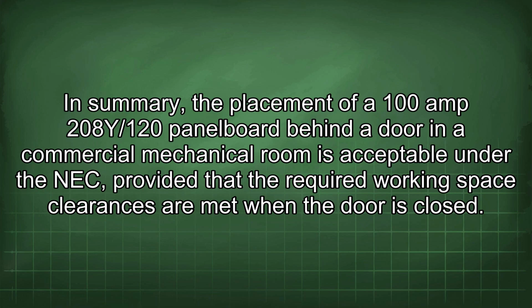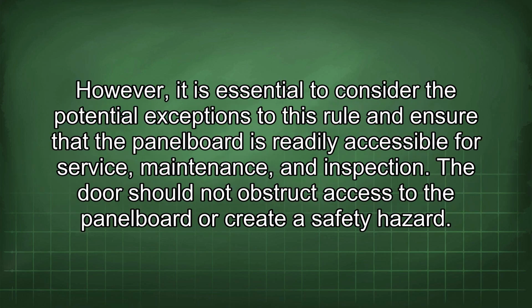In summary, the placement of a 100 amp 208Y/120 panelboard behind a door in a commercial mechanical room is acceptable under the NEC, provided that the required working space clearances are met when the door is closed. However, it is essential to consider the potential exceptions to this rule and ensure that the panel board is readily accessible for service, maintenance, and inspection. The door should not obstruct access to the panel board or create a safety hazard.